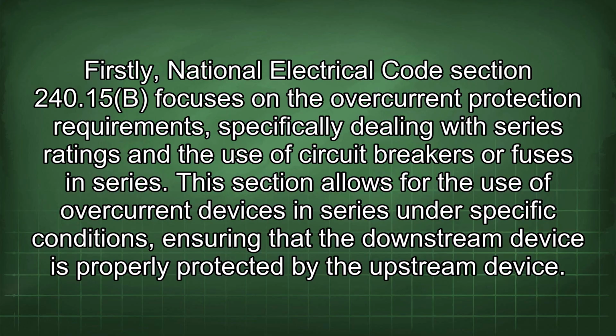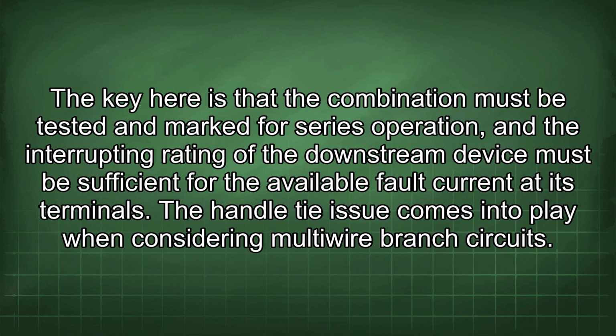This section allows for the use of overcurrent devices in series under specific conditions, ensuring that the downstream device is properly protected by the upstream device. The key here is that the combination must be tested and marked for series operation, and the interrupting rating of the downstream device must be sufficient for the available fault current at its terminals. The handle tie issue comes into play when considering multi-wire branch circuits.